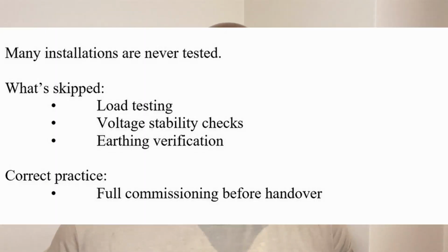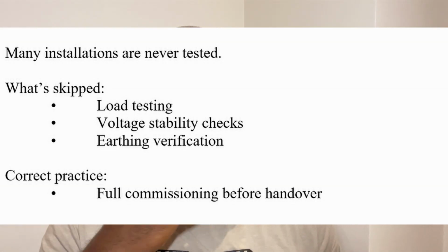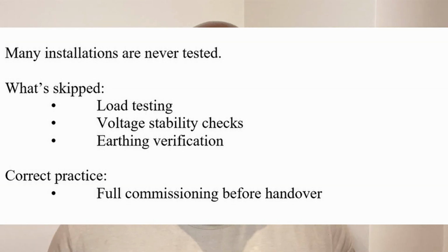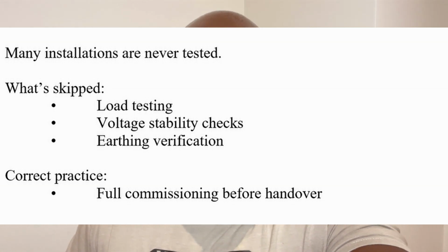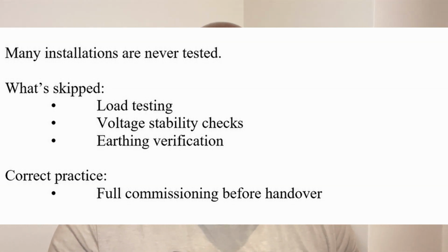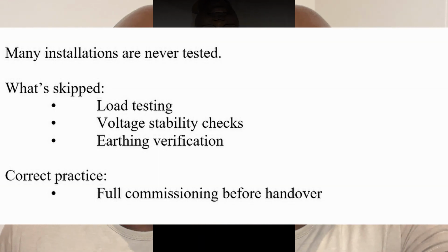Many installations are never tested. What is skipped? The load testing is skipped. The voltage stability checks are skipped. The earthing verification is skipped. The correct practice is full commissioning before handover. You want to make sure the system is tested. You want to make sure that the generator that you spent thousands and thousands of cedis or dollars to buy is working correctly, especially whilst you're still under warranty. Some issues may be that of the generator, some issues may be that of your electrical system. And the test will verify either way.